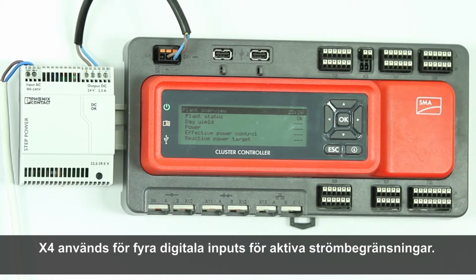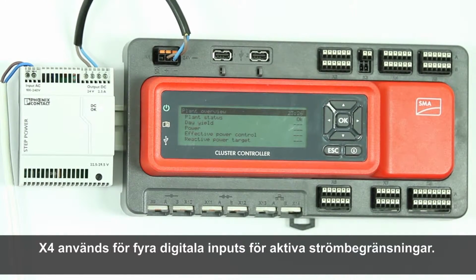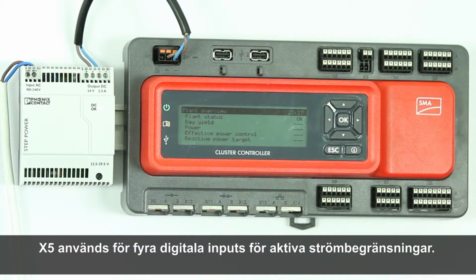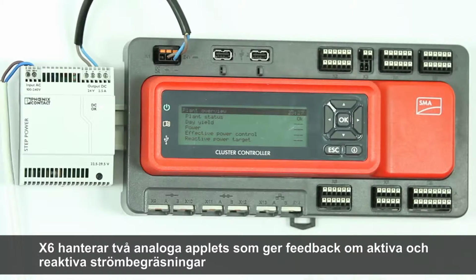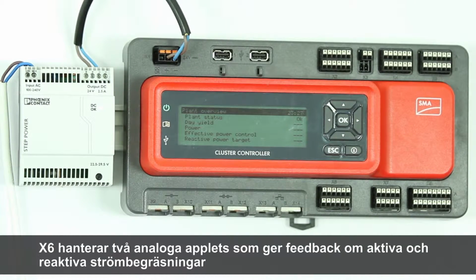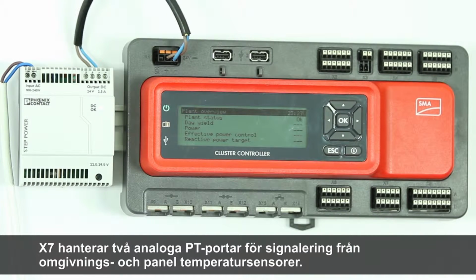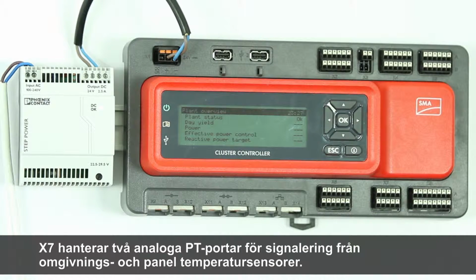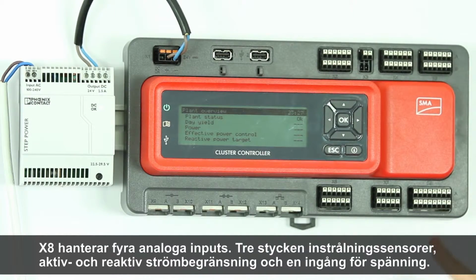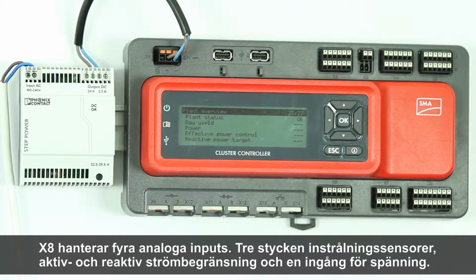X4 allows for 4 digital inputs for active power limitations. X5 allows for 4 digital inputs for reactive power limitations. X6 allows for 2 analog outputs for the feedback of current active and reactive power limitations. X7 allows for 2 PT ports for analog signals from ambient and module temperature sensors. X8 allows for 4 analog inputs, 3 current inputs for the radiation sensor, active and reactive power limitations, and 1 voltage input for connection of a sensor.